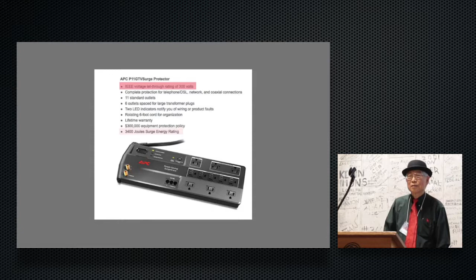One thing to look for, not always specified, is feed-through voltage. It means when 6,000 volts is applied to the connector, what shows up here? In this case it says 300 volts, which isn't bad, since European power is 240, so it's not far from that.